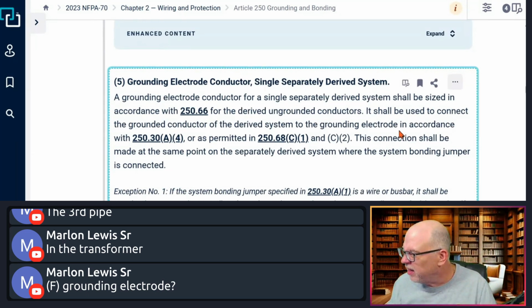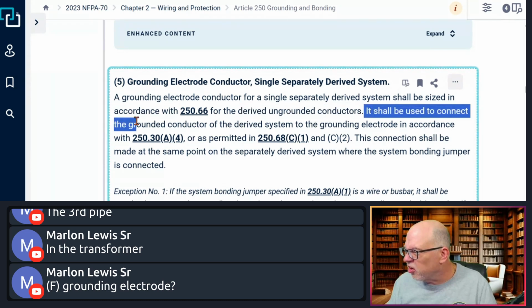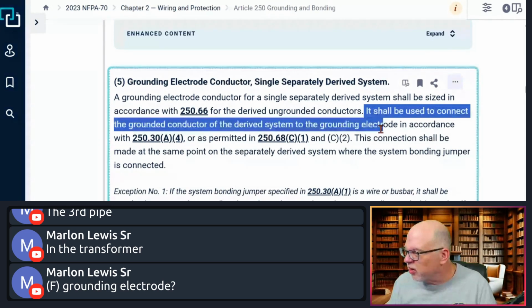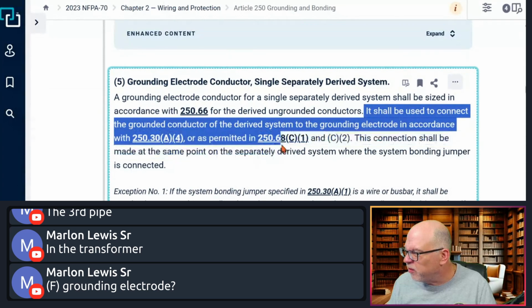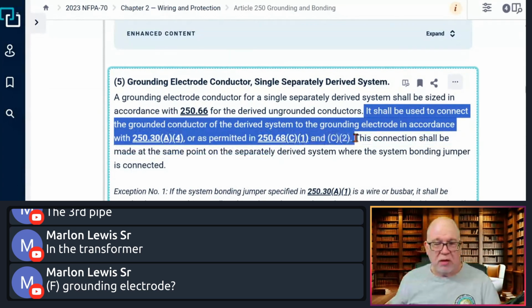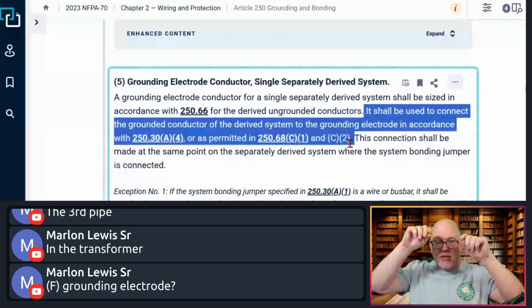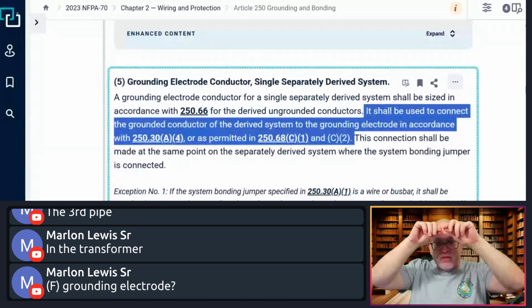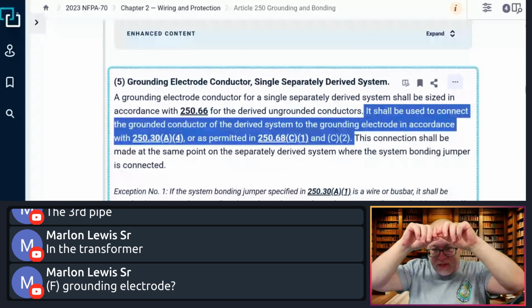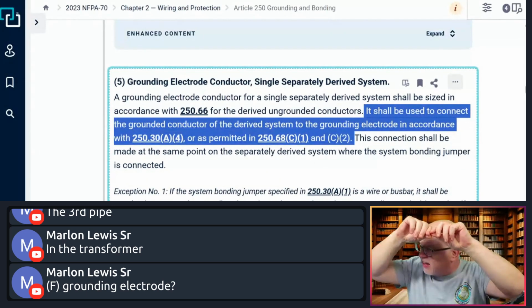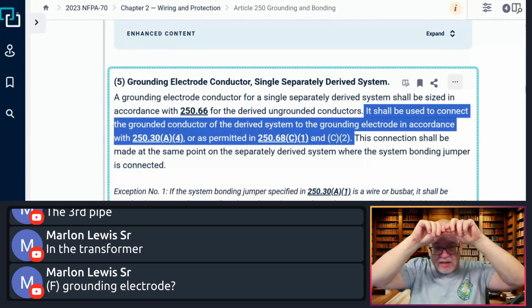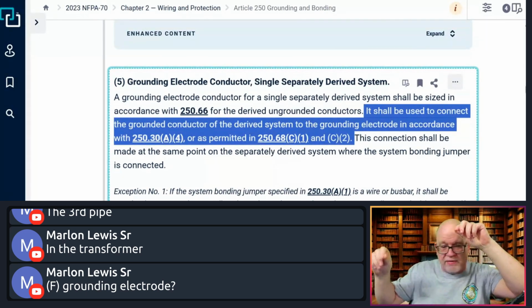Okay, easy peasy. It says it shall be used to connect the grounded conductor of the derived system to the grounding electrode in accordance with 250.30(A)(4) or as permitted in 250.68(C)(1) through (C)(2). So that connection, that grounding electrode conductor, is what's going from the XO or from the system. In this case, it's used to connect that grounded conductor all the way down to the electrode, whatever that may be. So that's what it's being used for.